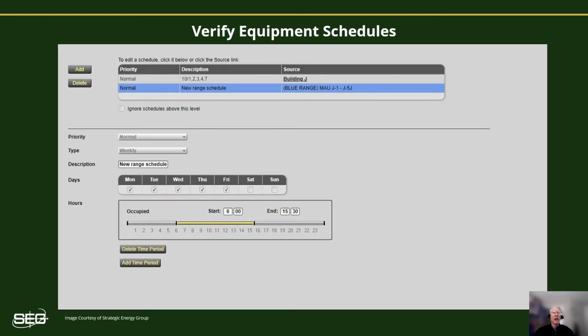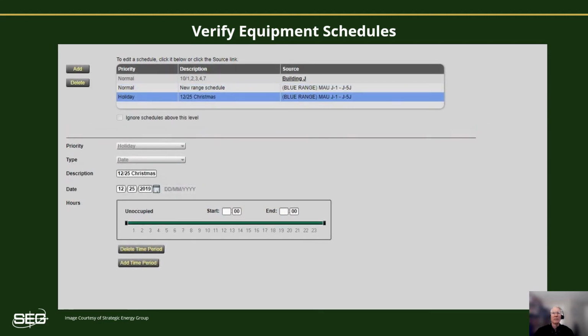After this video, I highly encourage you to check and confirm what the current schedules for the HVAC and lighting in your building are set for. You may be surprised. We recommend setting up pre-scheduled work orders in your PM system to regularly review, verify, and update any changing equipment schedules. These should be scheduled on a quarterly basis at a minimum.